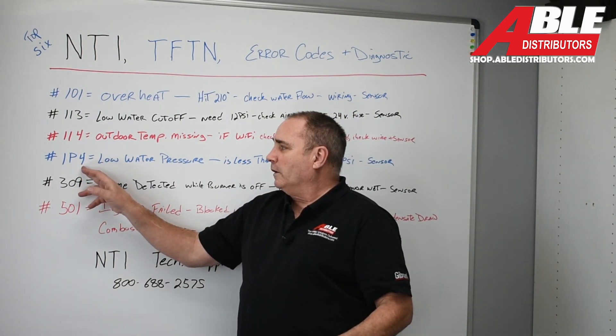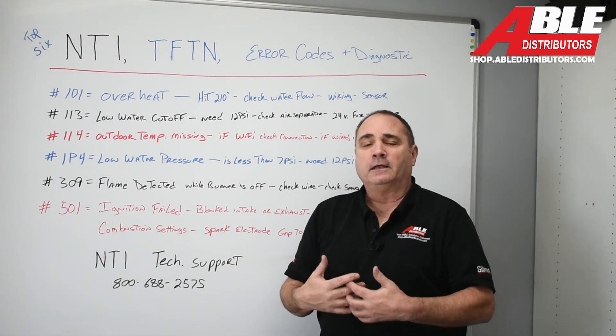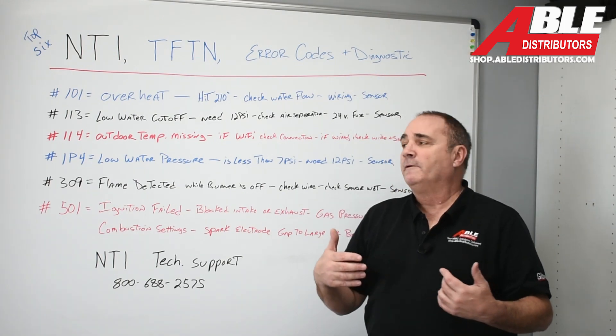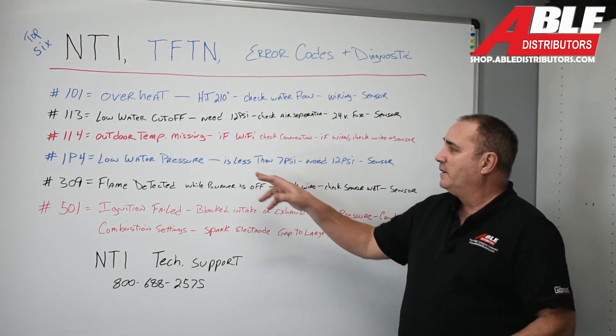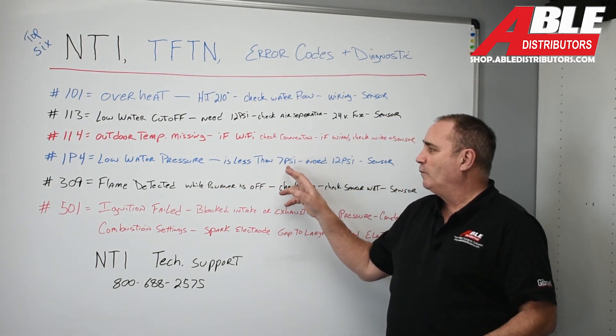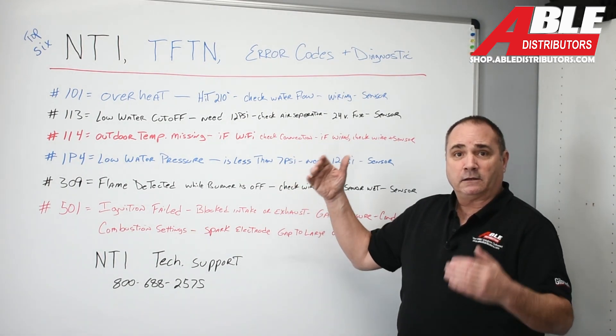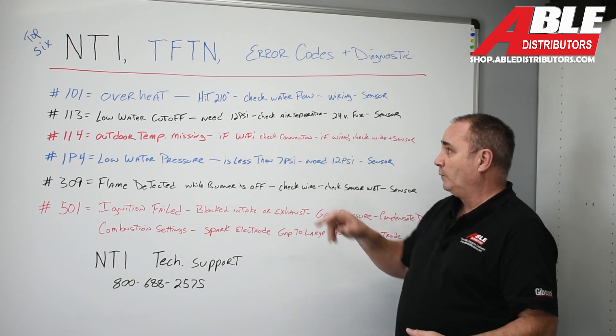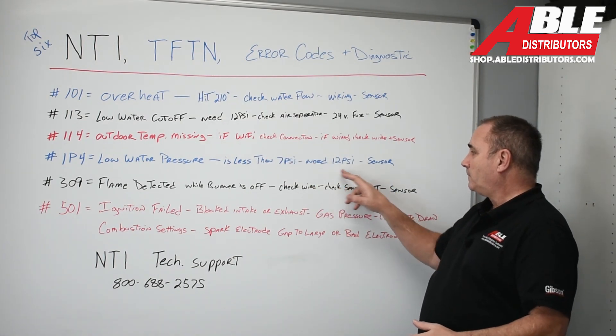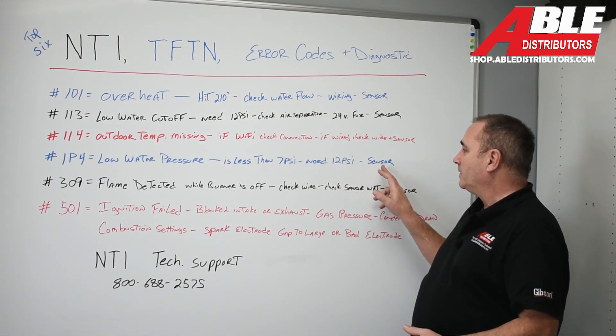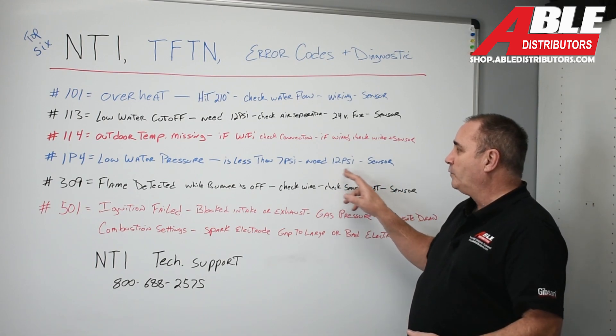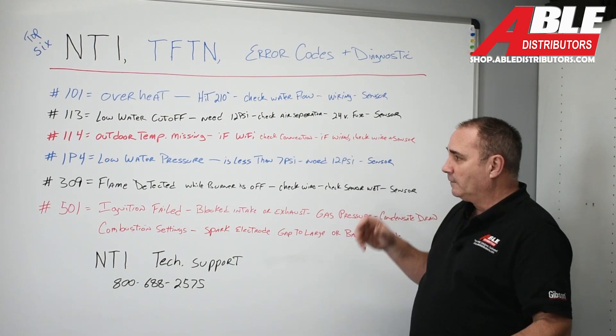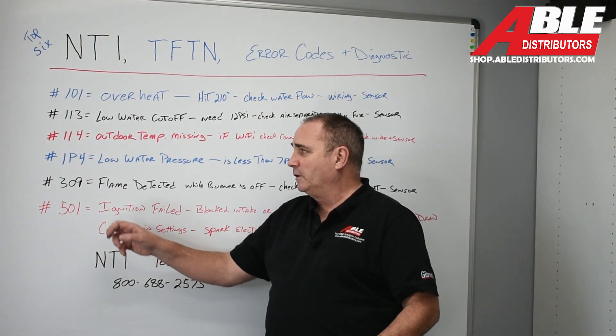Code 1P4: low water pressure. Make sure your fill valve is operating properly. This typically triggers if you go below 7 psi — that's low. We want 12 psi. Once you bring it up to 12 psi, if it's still showing this code, it might be the sensor. Tech support would be good for that.